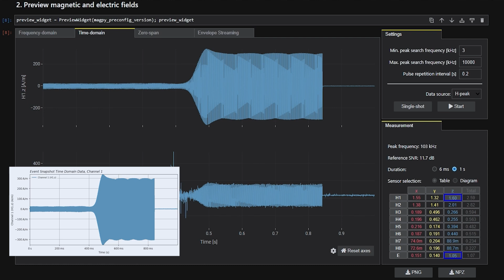Next, I capture an event snapshot while removing the phone away from the charger. The snapshot clearly shows that the charging stops at the end of the 1 second duration, confirming that the transmitter of the charger shuts down within 1 second. ISED requires a transmitter shutdown time check for the nerve stimulation compliance testing. For documentation purposes, I save the snapshot as a PNG file, which can be included in the compliance test report.